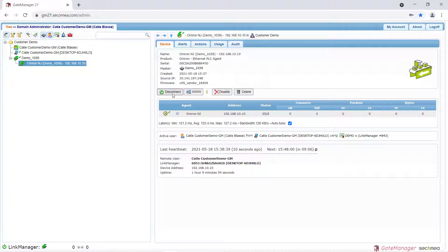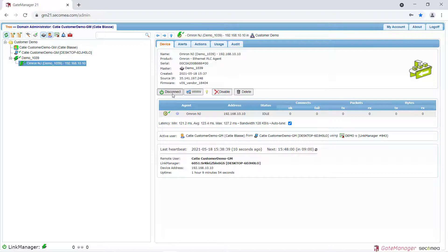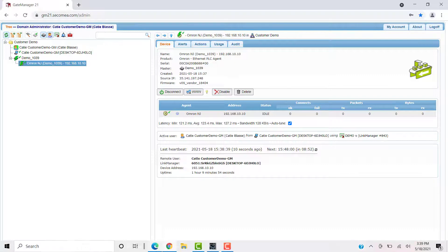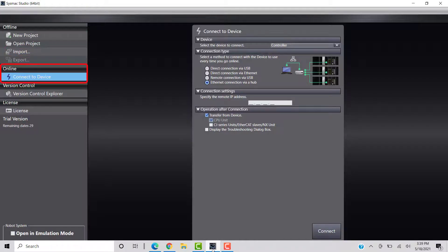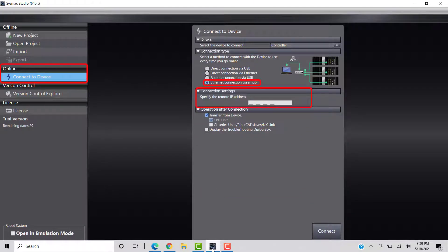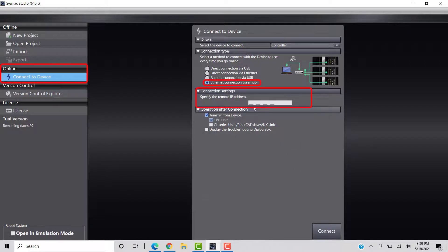Now that we are connected to the Omron controller through Link Manager, we can connect to the device in the Omron SysMac software, just as if we were connected over our local network. Open the SysMac software. Click Connect to Device and select Connect to Device through Ethernet. In the Connection settings, enter the IP address of the controller.